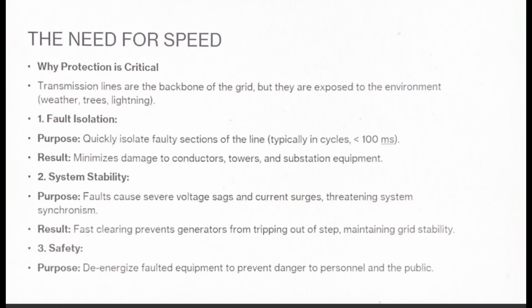So for the first slide, the need for speed. The moment a fault occurs, a lightning strike, a tree branch hitting a line, we enter a race against time. The primary law of protection is threefold, and speed is key to all of them. So first is fault isolation. The entire goal is to isolate that tiny section of the line where the fault is located. We're talking about operating in cycles, typically less than 100 milliseconds. If the fault is allowed to burn for too long, it can permanently damage high voltage conductors or even cause a tower to collapse.